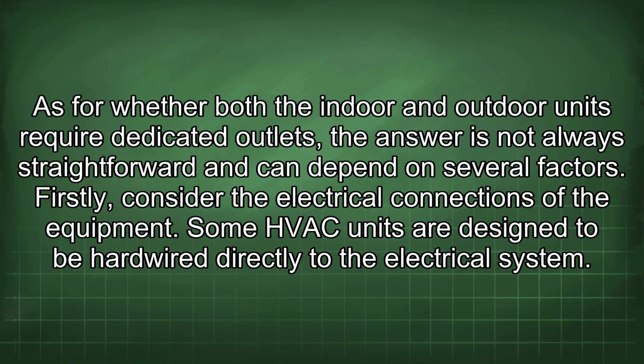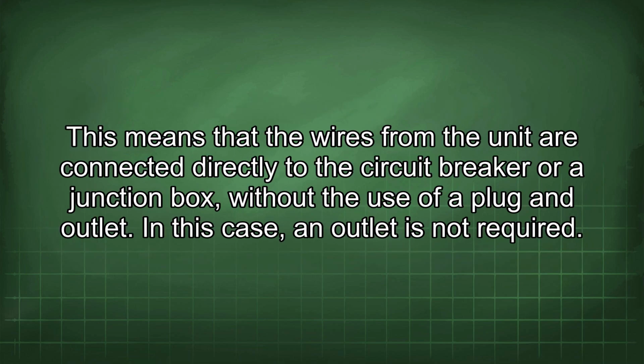As for whether both the indoor and outdoor units require dedicated outlets, the answer is not always straightforward and can depend on several factors. Firstly, consider the electrical connections of the equipment. Some HVAC units are designed to be hardwired directly to the electrical system. This means that the wires from the unit are connected directly to the circuit breaker or a junction box without the use of a plug and outlet. In this case, an outlet is not required.